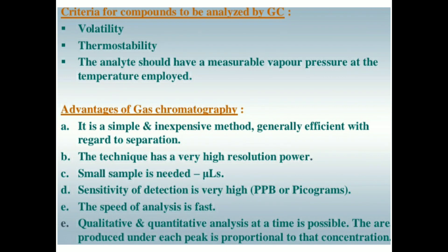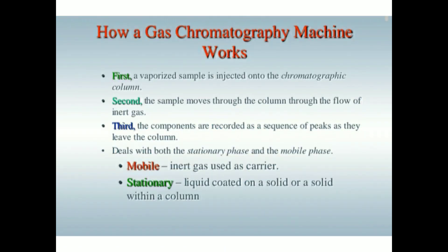How a gas chromatography machine works: first, a vaporized sample is injected onto the chromatography column; second, the sample moves through the column; third, the components are recorded as a sequence of peaks as they leave the column. The technique deals with both the stationary phase and the mobile phase — the mobile phase is an inert gas used as a carrier, and the stationary phase is a liquid coated on a solid or a solid within a column.